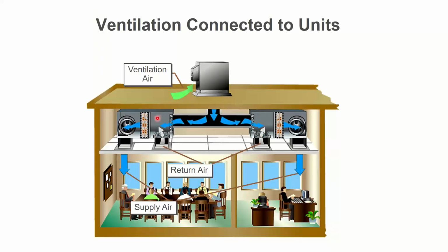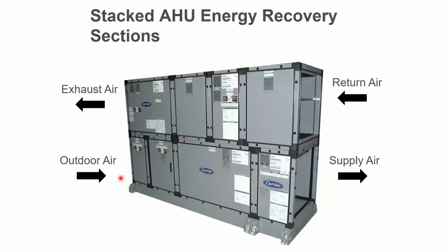One way would be to duct it into the fan coil. Instead of dumping it in separately, bring that guy in and dump him into the fan coil, mix him with the return, then heat and cool him further if needed, and distribute it to the space. That's probably a better way to do it. You can build an ERV into the air handler itself. So this is fairly common also. It's going to be a stacked air handler.